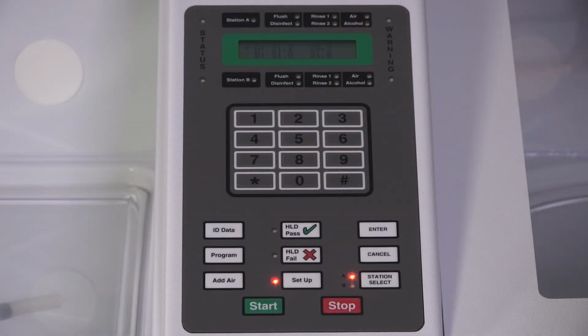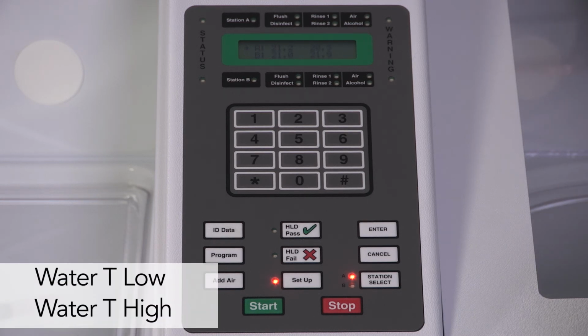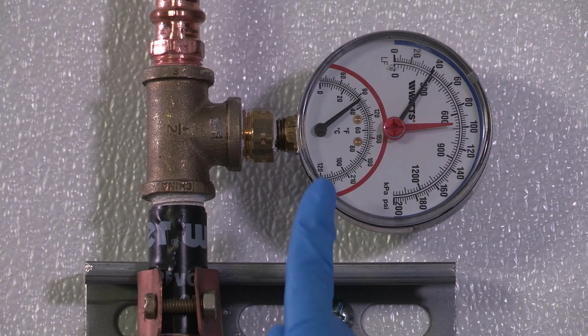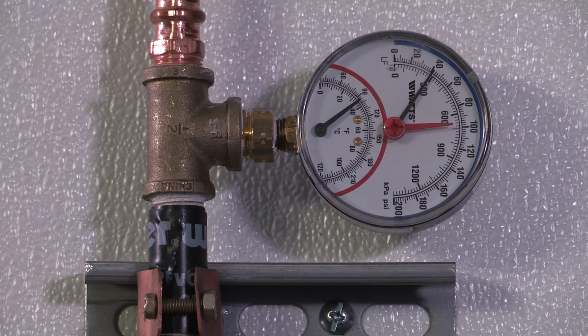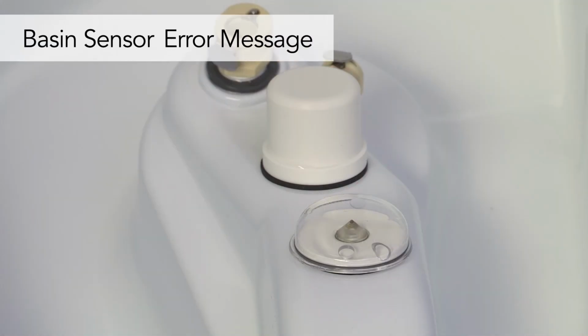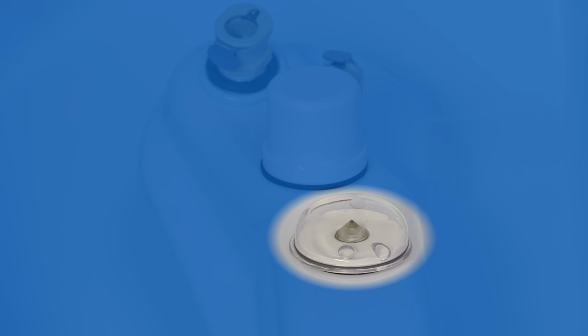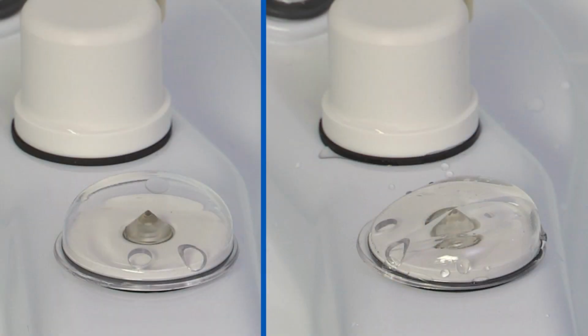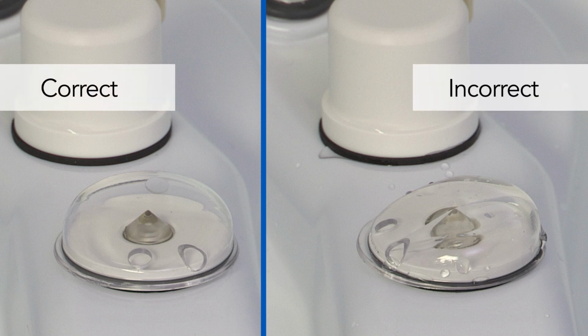When the incoming temperature is below 30 degrees or above 40 degrees Celsius, the display will show water T low or high, respectively. Call your facility maintenance to troubleshoot your incoming water temperature and mixing valve. A Basin Sensor error indicates fluid on the Basin Sensor, located inside the basin on top of the manifold. The cap should be placed so that the single hole is at the 12 o'clock position, and the other holes are at 5 and 6 o'clock.